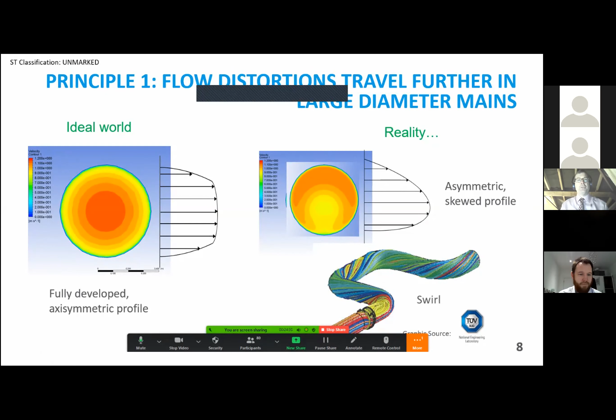But what happens is, as water goes through fittings, as it goes around bends, flow becomes distorted. And what we can see is that high velocity can be sent to one side of the main. And also in larger mains, we can get swirl, and we see skewed profiles. These skewed profiles can make it more difficult for meters to read accurately. And in larger mains, because the ratio between the pipe wall and the area is greater, these distortions go on longer, much longer than we get in smaller mains.